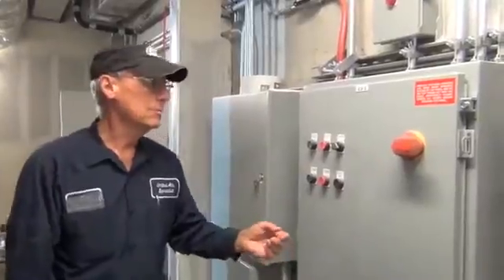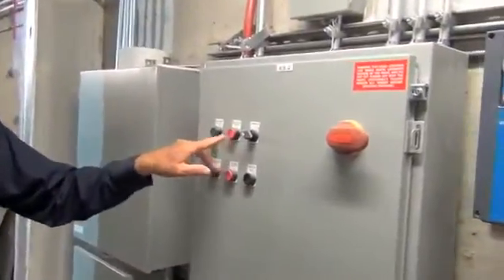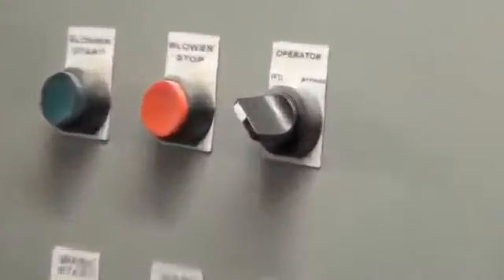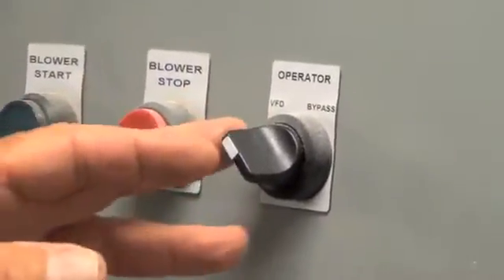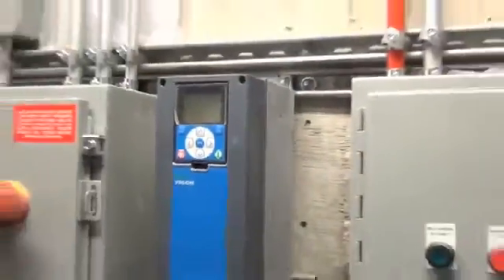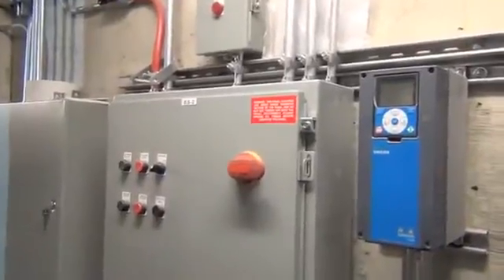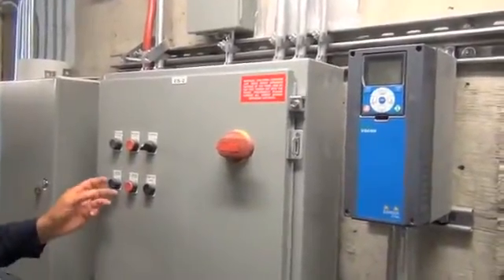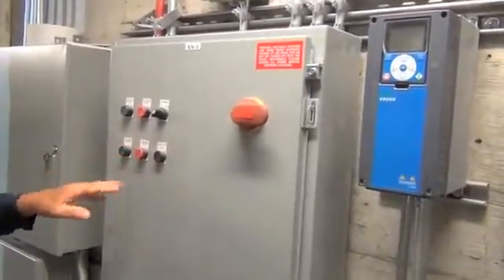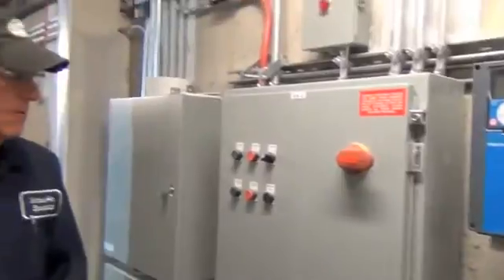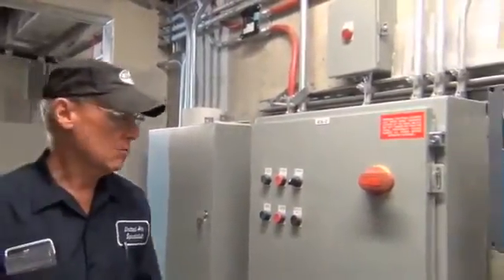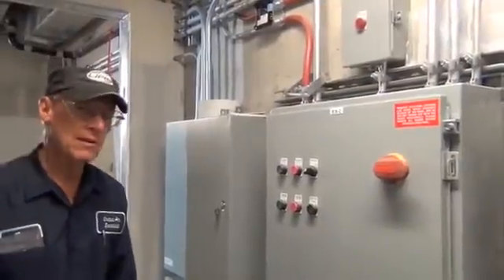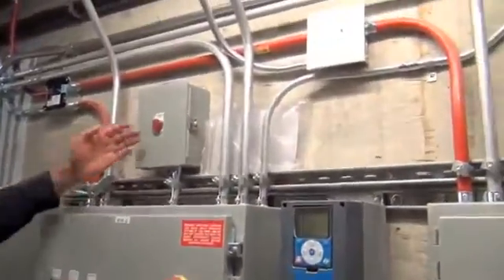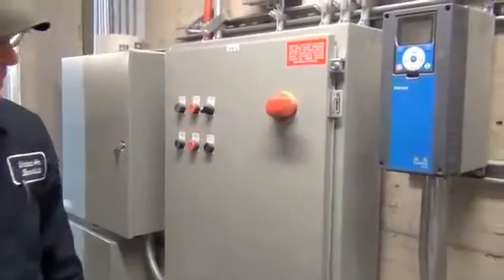This is a UAS main electrical control panel. On this control panel we have several push buttons. We have the main buttons for blower start, blower stop for the Smog Hog. On this particular panel we have a VFD. The VFD is operated in this particular mode, and then the bypass, in case we have failure in the VFD, we can put it in bypass. Wash start, wash stop. Also with these buttons you have a time clock that you can program the wash cycle. Power pack reset is when we have a power pack alarm. We have a duration of 60 minutes. After 60 minutes we'll have an alarm on this indicator panel. Main disconnect on and off for the electrical panel.